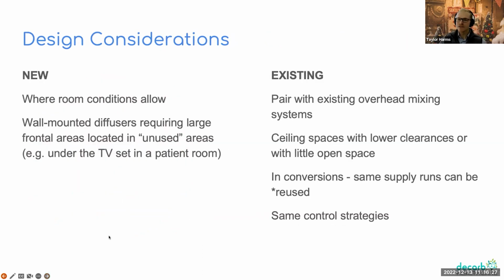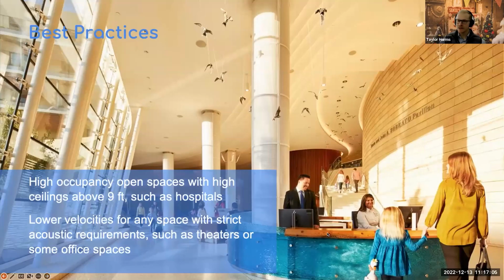Design considerations, you can use displacement ventilation in both new construction and in renovations as well. The greatest consideration, regardless of the application, is you can only use it where the room conditions allow. So this could be the architectural features of the room or the loading of the room as well. But it does allow you to use previously unused spaces, such as underneath a TV set. You could place a supply diffuser right there.